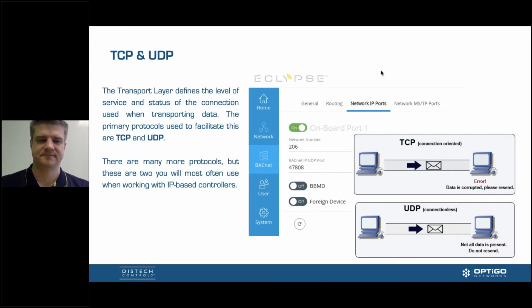So basically, the TCP is kind of like that email that would be sent out. You know, the data integrity is very important. There's an acknowledgement on the other side that information gets sent, and it needs to know that it is there and it needs to be there. Anything you download and keep for long-term storage, that is going to be done under a service of TCP. The UDP, on the other hand, and this is where we take advantage of in the HVAC world over IP, UDP lets us handle things like broadcasts, for example.